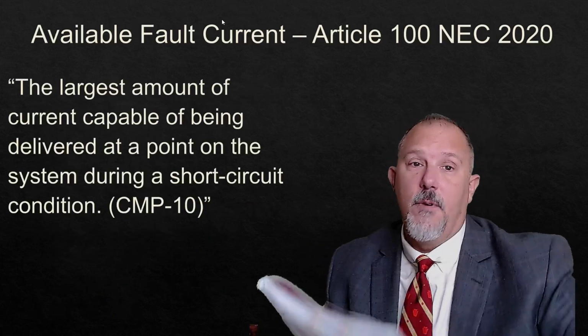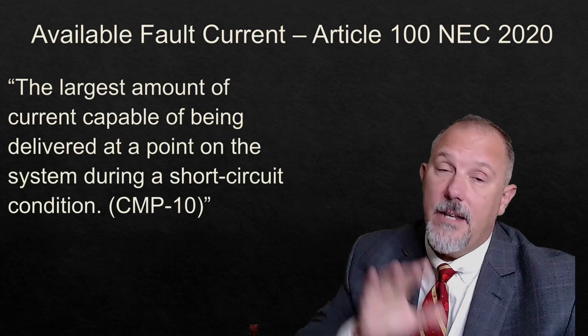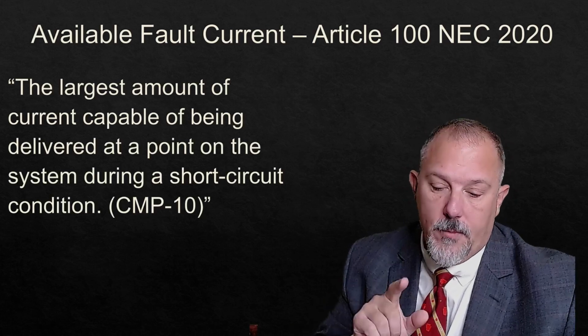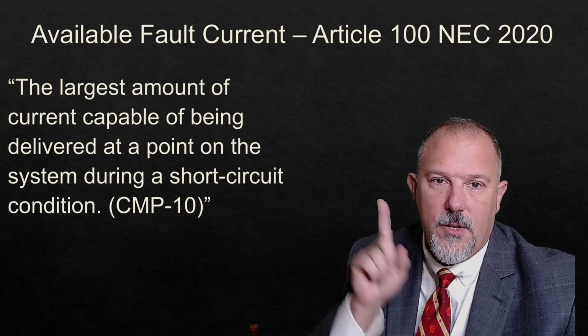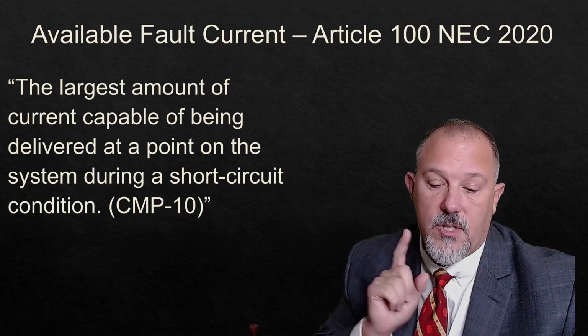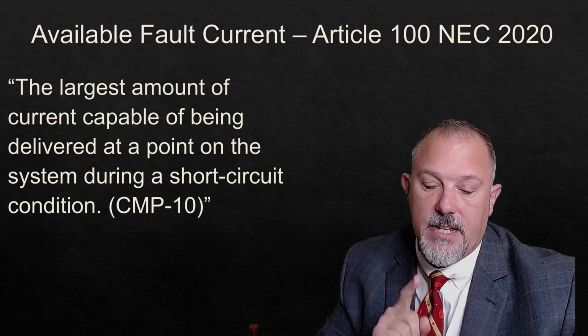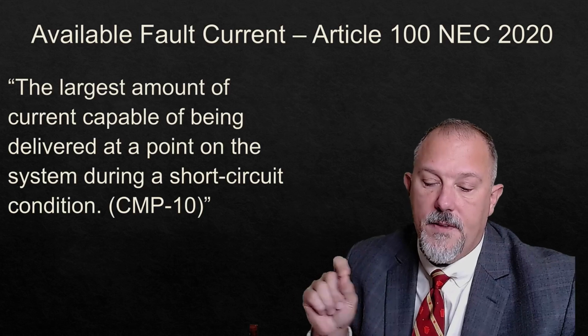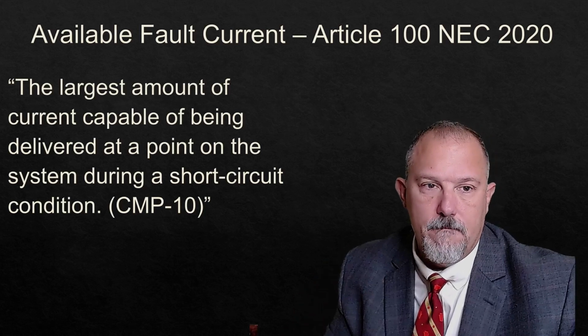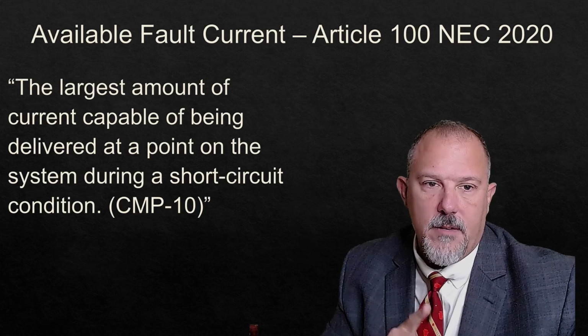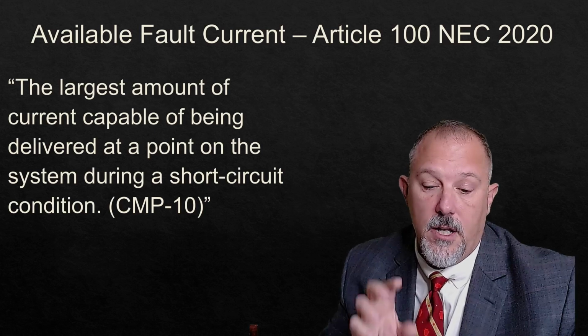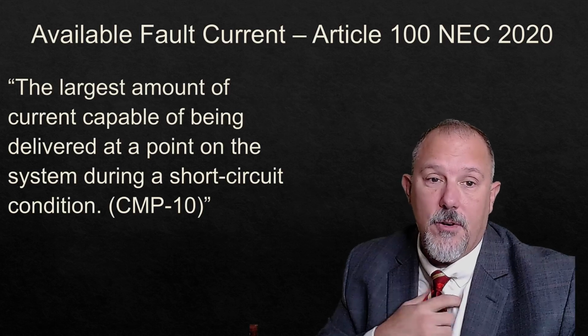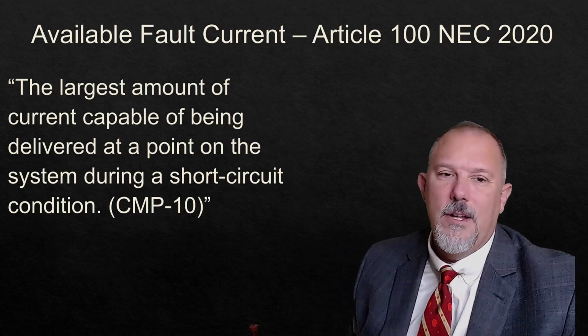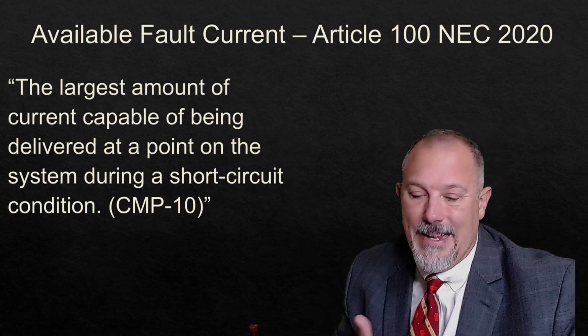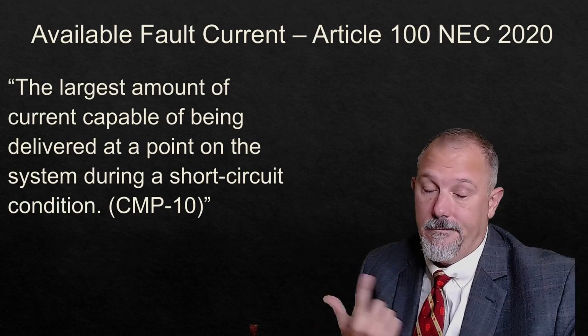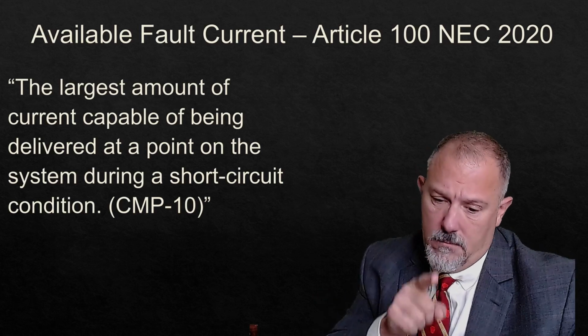All right, so available fault current is another defined term. I'm going to read to you what it says in 70E, and you can watch this, which is what's in the National Electrical Code. 70E says, the largest amount of current capable of being delivered at a point on the system during a short circuit condition. So it looks like it is verbatim, and I would argue that maybe to follow the style manual requirements, that definition should show that it is extracted text. I don't know. David Williams, if you're out there, buddy, check into that.